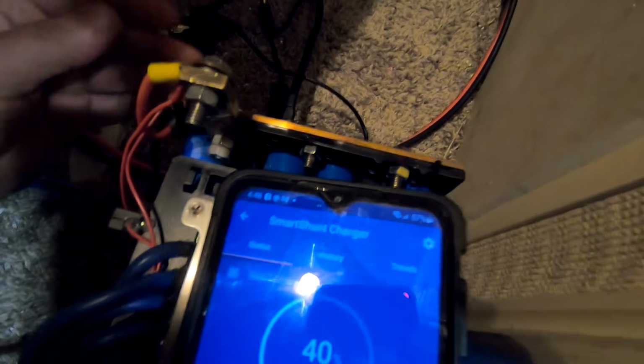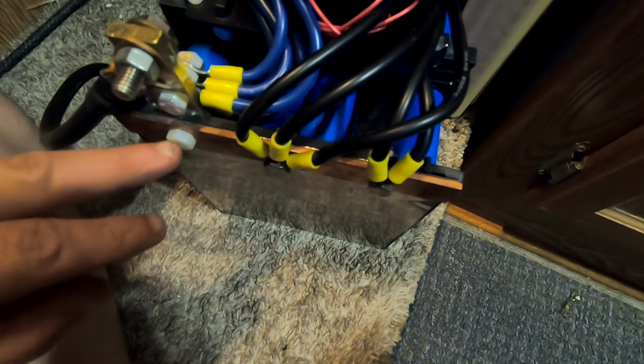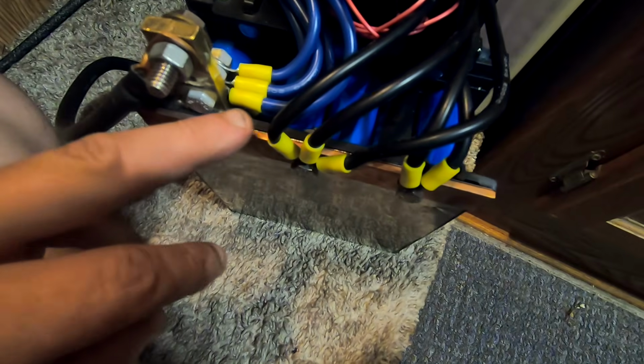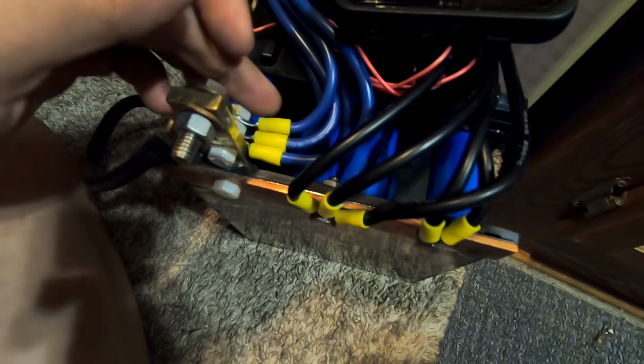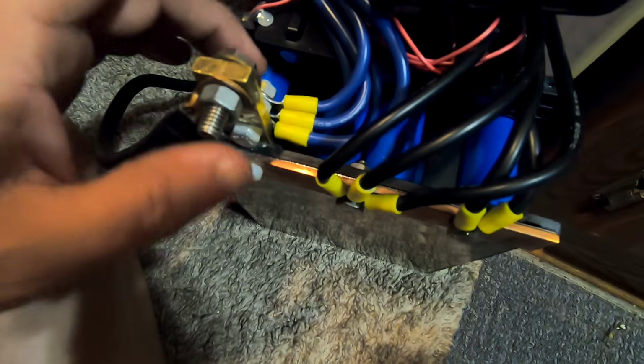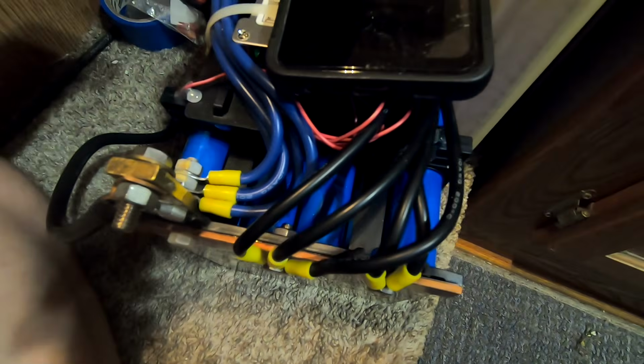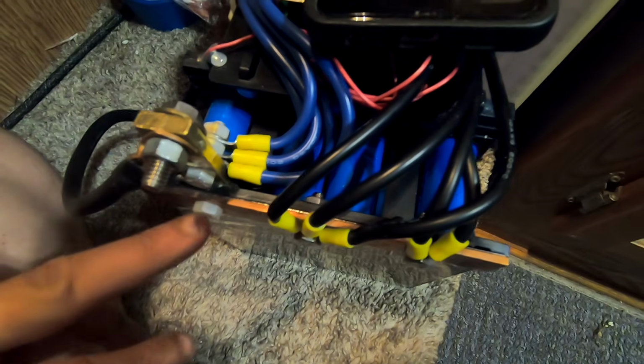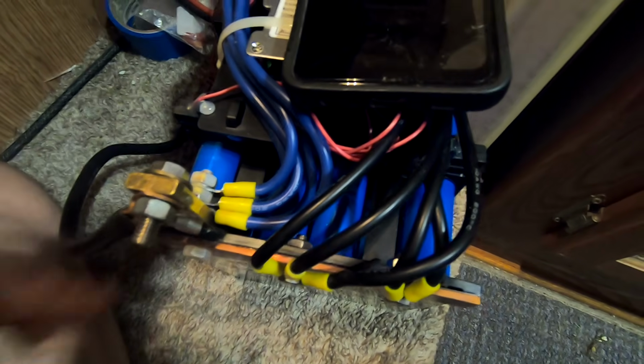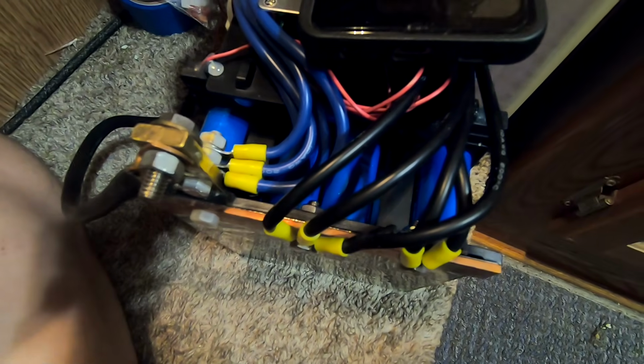This one is on a plastic nut, so I didn't tighten it, because it needs to be insulated from this bus bar, since this is what comes from the batteries to this connection here where the terminal is. So it has to be insulated from it so the BMS does its job. Otherwise, if this was a metal bolt, the BMS would be pointless and it would be going constant.